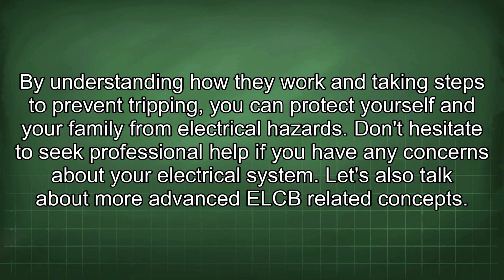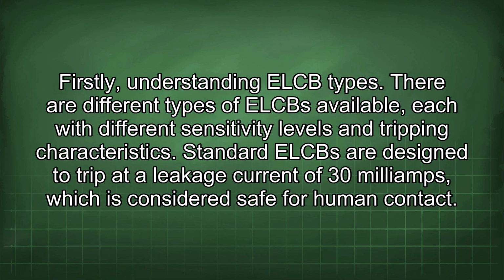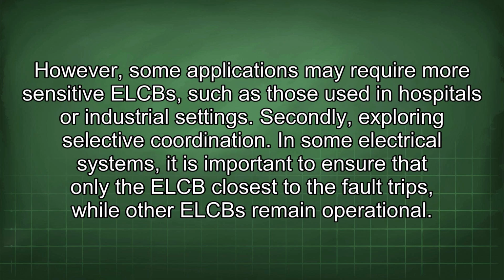Let's also talk about more advanced ELCB-related concepts. Firstly, understanding ELCB types. There are different types of ELCBs available, each with different sensitivity levels and tripping characteristics. Standard ELCBs are designed to trip at a leakage current of 30 mA, which is considered safe for human contact. However, some applications may require more sensitive ELCBs, such as those used in hospitals or industrial settings.